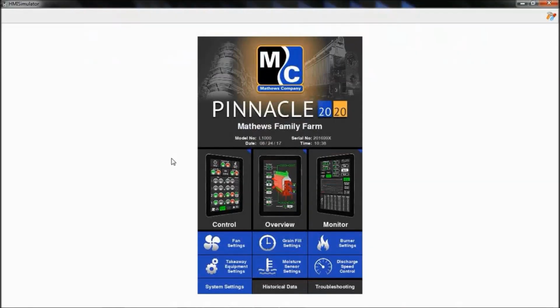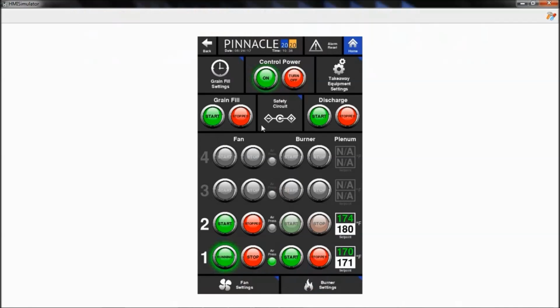So let's run through a few simulations of how we can use that screen to identify a problem. There's a couple ways to get to this. We can go to troubleshooting. We have our safety circuit button right here. Alternately, we can be on our control page. Let's say we come to the dryer and it's off, and Mike will go ahead and trip an alarm. We'll throw a high limit or something. Or E-stop's fine, sure. So we went ahead and threw an E-stop, and we can see from the control screen that we cannot latch control power, and we can see that because the buttons aren't illuminated.